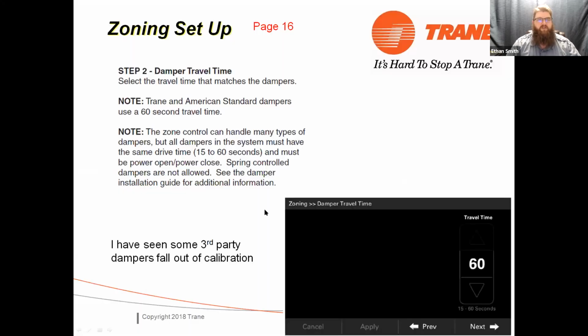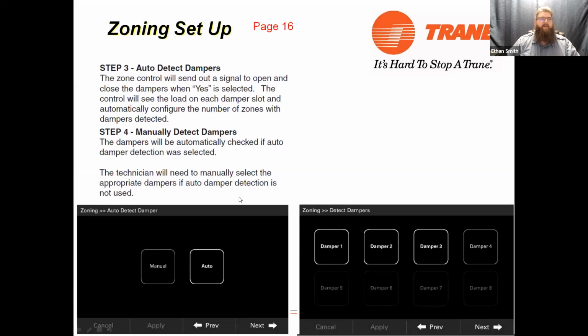Okay. So once you enable zoning, it will launch you into the zoning setup. First thing it's going to ask you is your zoning damper travel time. It defaults to 60. If you're using Carriers, set it to 15. Just make sure that all your dampers have the same timing guides. After that, it wants to know if you want to auto detect dampers. If you select auto, it will power all the dampers open for 30 seconds and then power them all closed for 30 seconds. While it's doing this, it's looking for amp draw on the relays for each bank of dampers. If it sees amp draw on both the power open and the power closed signals, it will automatically detect your dampers. So it'll say damper 1, 2, and 3 in this case. It detected dampers on zones 1, 2, and 3.